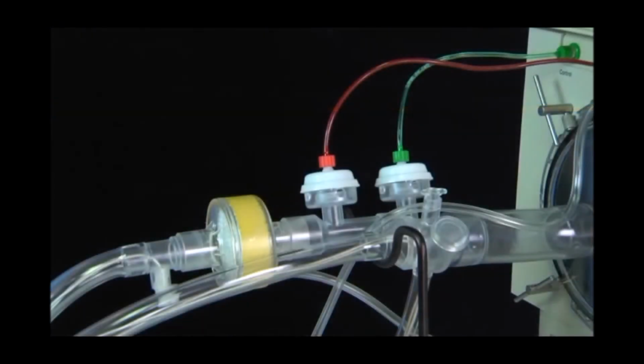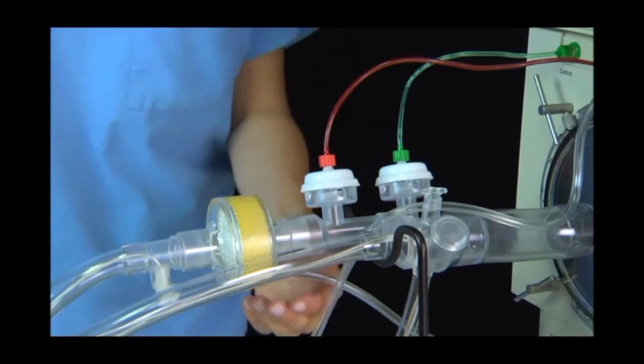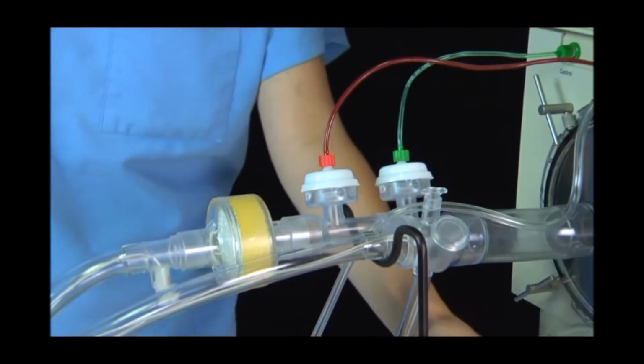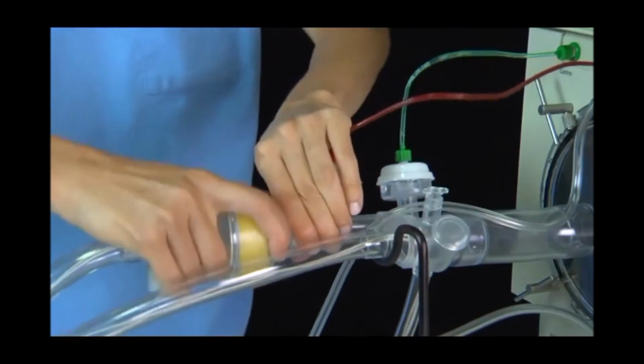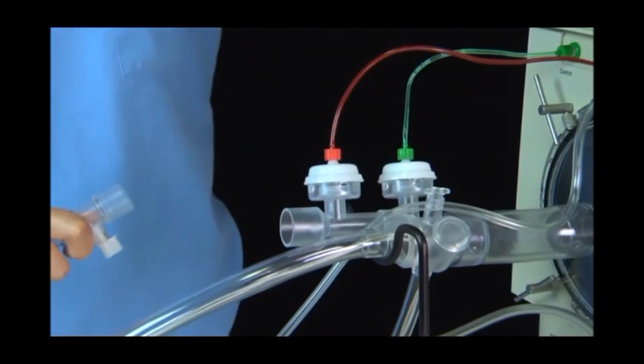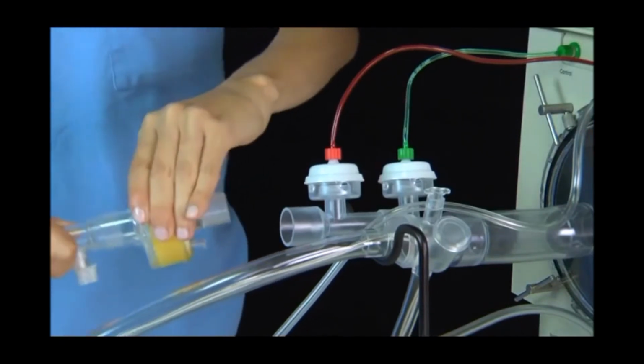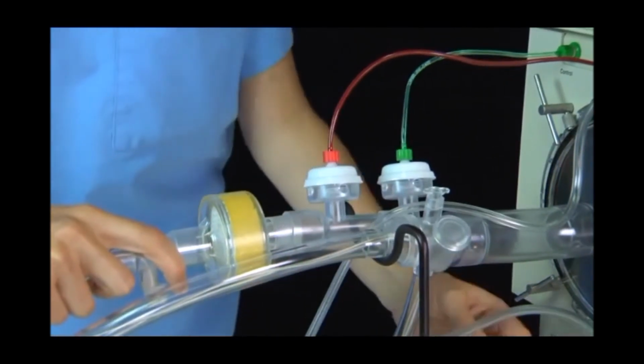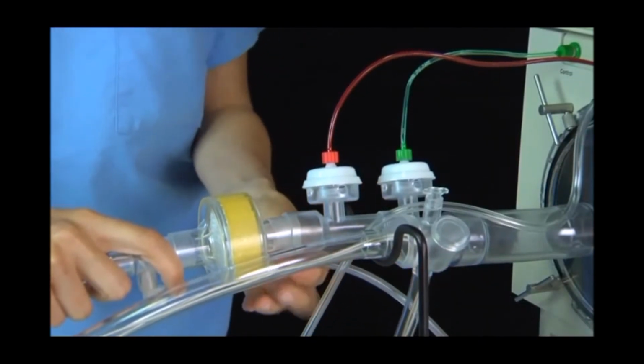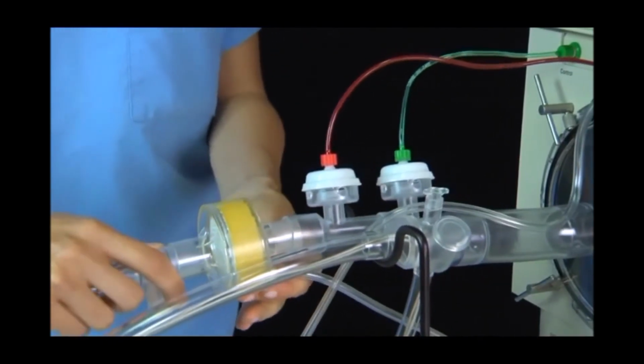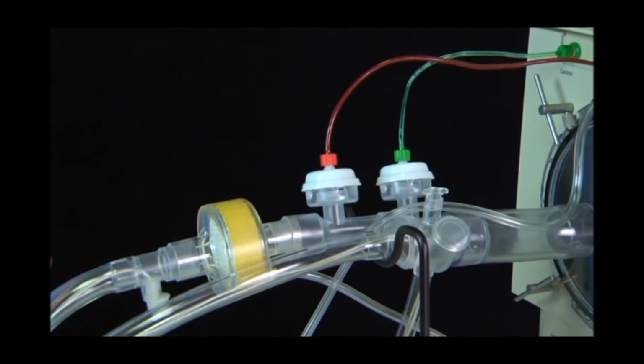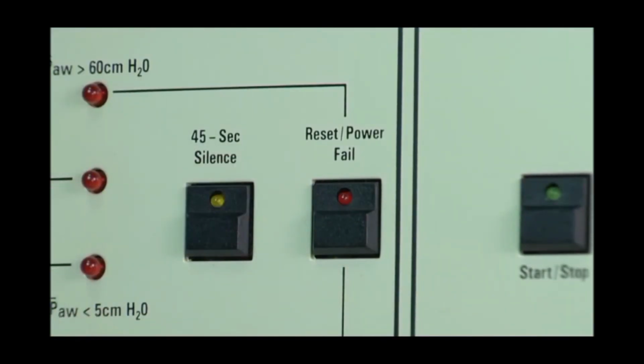Prepare the new filter by removing it from its packaging and place it in an accessible place such as on top of the 3100 or a bedside tray. Disconnect the water trap drain tubing from the luer fitting on the bottom of the filter. Carefully disengage the filter from the circuit and set aside. Place the new filter in the circuit. Reconnect the water trap drain tubing to the luer fitting on the bottom of the filter. Ensure all connections are hand snug, but do not over-tighten. Reconnect patient if needed, and depress the reset button to pressurize the circuits and resume ventilation.